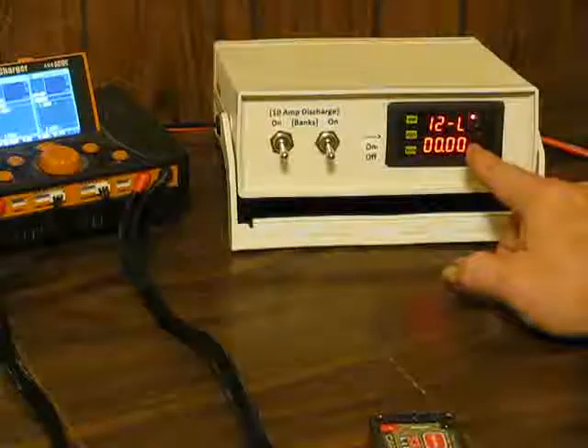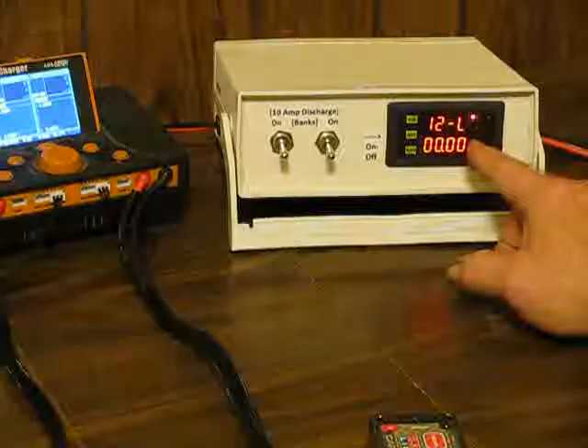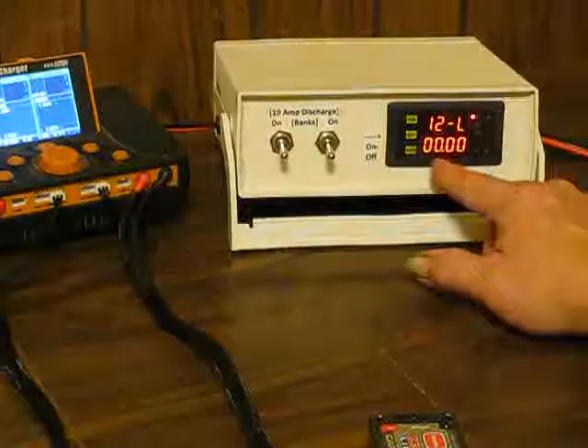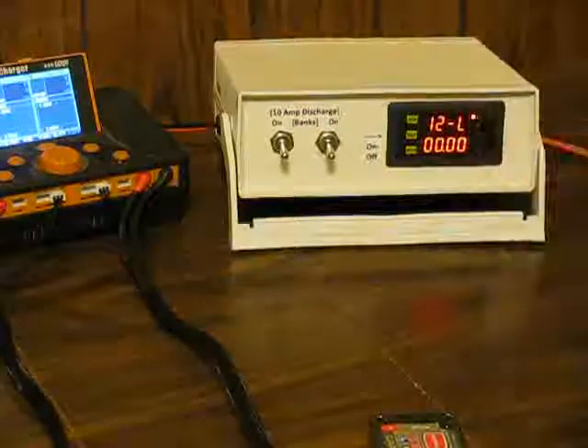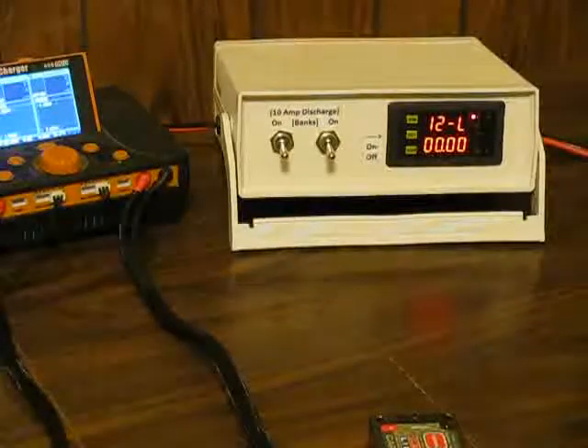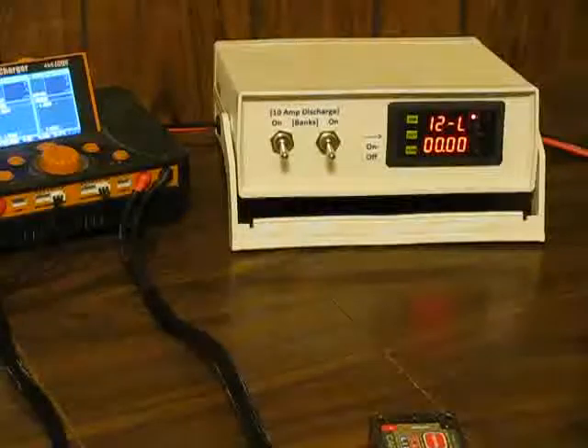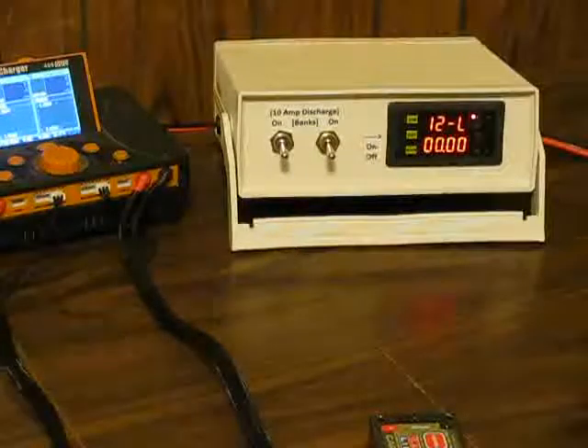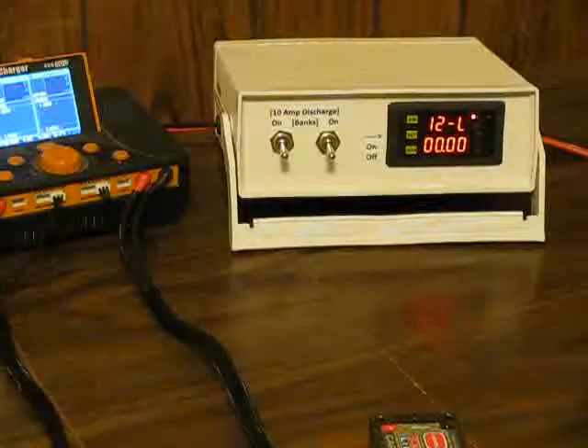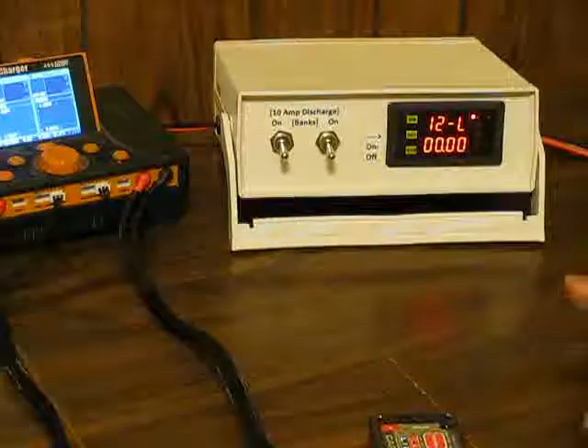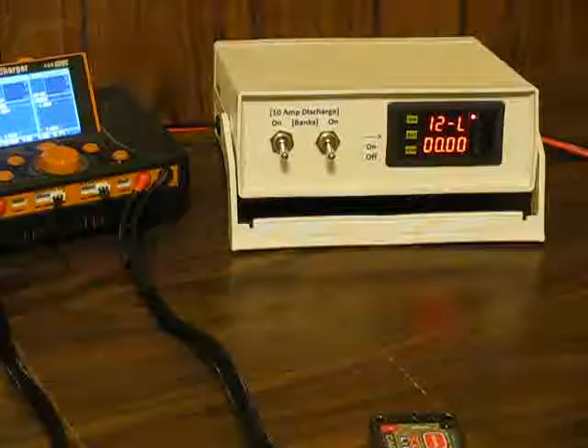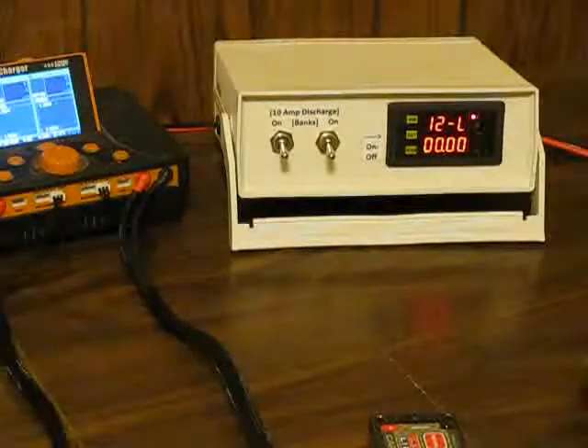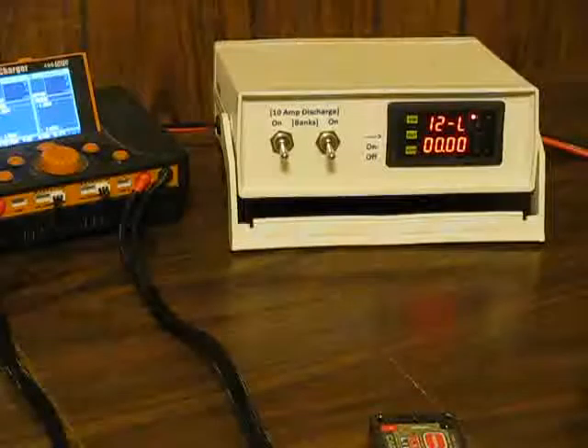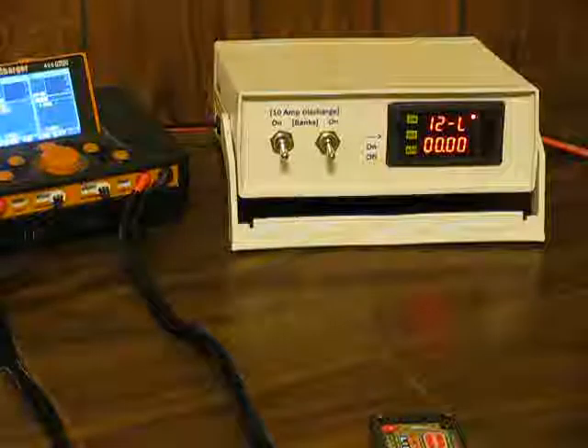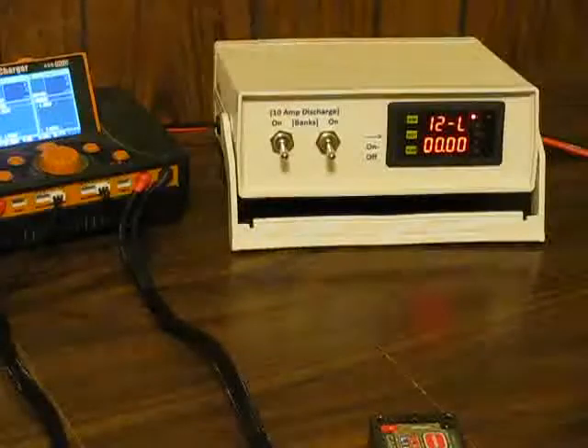Setting 12 is the one you need to know — this is your low voltage shut-off point. For right now, we're going to set it at about 8 volts, and there's a reason for that in the calibration process. Honestly, when we discharge a battery, it'll be set at 6.97 or 6.96 volts, but for right now we'll set it at 8.